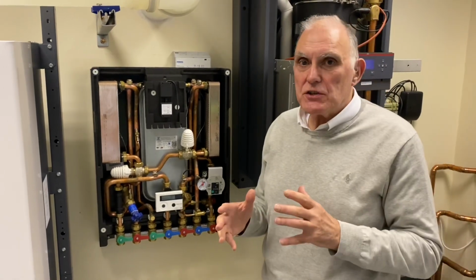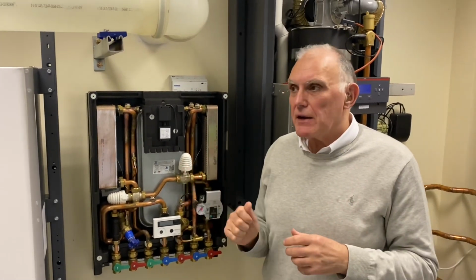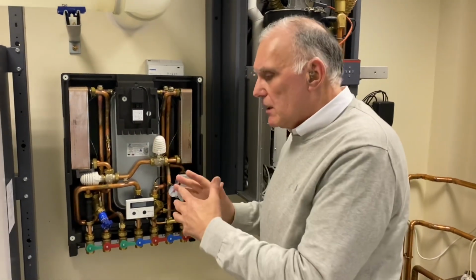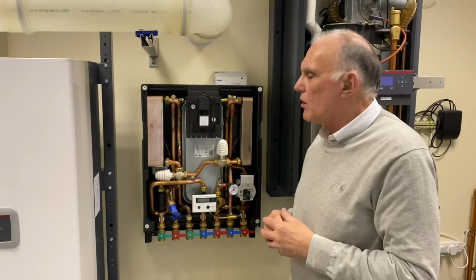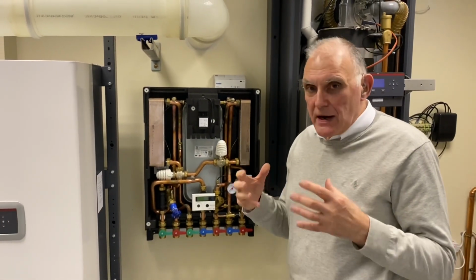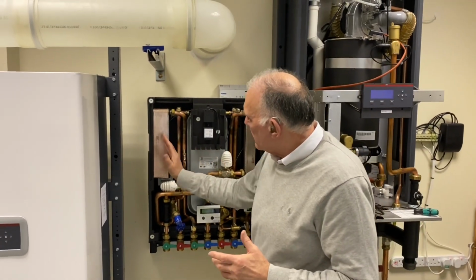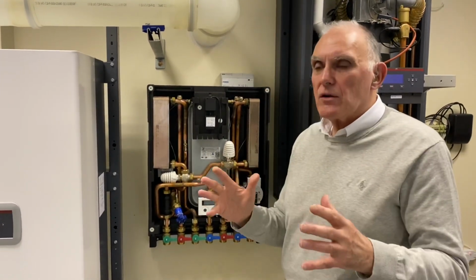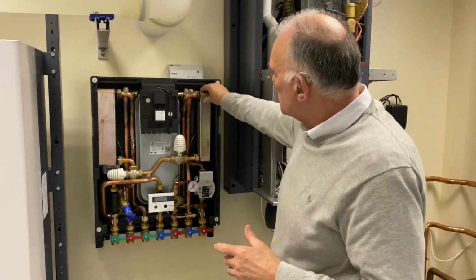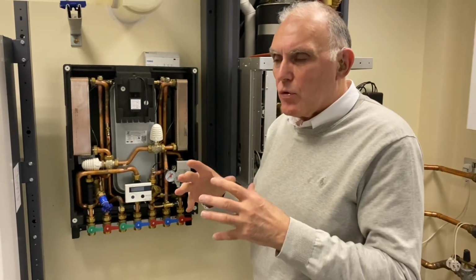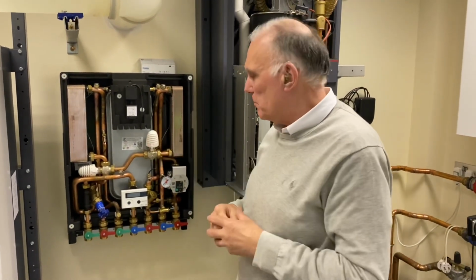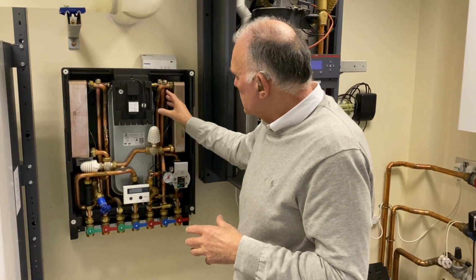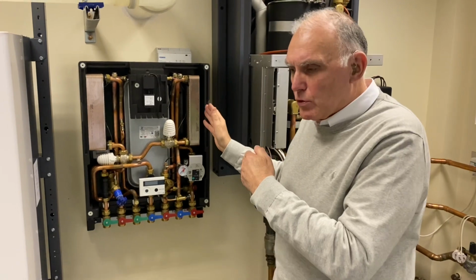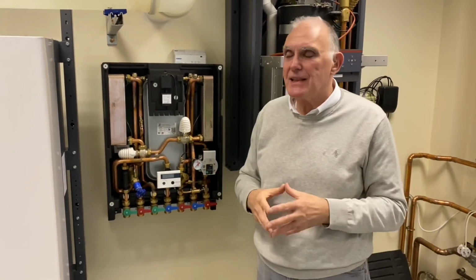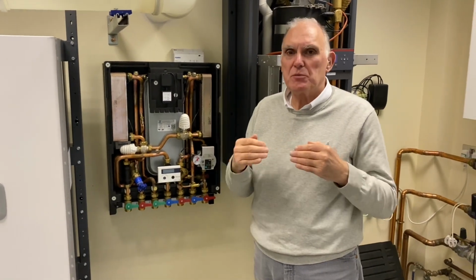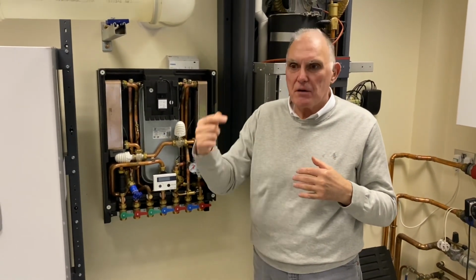I'd just like to go back and mention a direct unit. This is an indirect unit because the heating system is indirect to the main flow returns, as is the domestic hot water system. There are direct systems, and that means this side of the HIU would remain unaltered. But on a direct system, we don't have a second plate heat exchanger here. The primary water that is circulating around the apartment block is circulated into this section, but there's no plate heat exchanger. So the water that circulates throughout the building, throughout the space heating in that building, is at the same temperature as the primary water in the main flow returns.